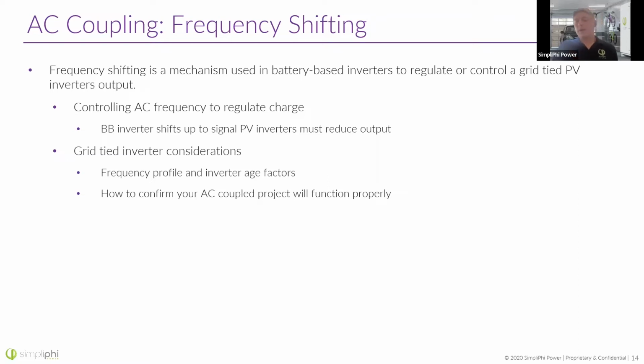Another thing to think about here, though, is if you're installing a brand new battery-based inverter and you've got 10-year-old microinverters on your roof, are those compatible? So you've got to check into that. You've got to call the manufacturers and ensure that both the inverters are compatible and that they even have frequency shifting capabilities if it's older. All the newer ones, of course, will have this, but the older inverters sometimes do not have this.